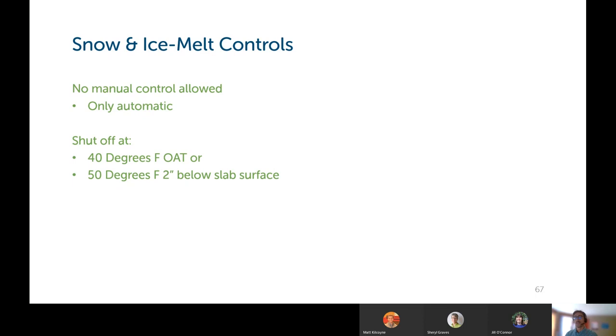Snow and ice melt controls. There is no more manual control allowed for snow and ice melt controls, only automatic. You need to either have it shut off at 40 degrees Fahrenheit outdoor air temperature, or 50 degrees Fahrenheit measured 2 inches below the slab or sidewalk, whatever the surface is that is being heated.